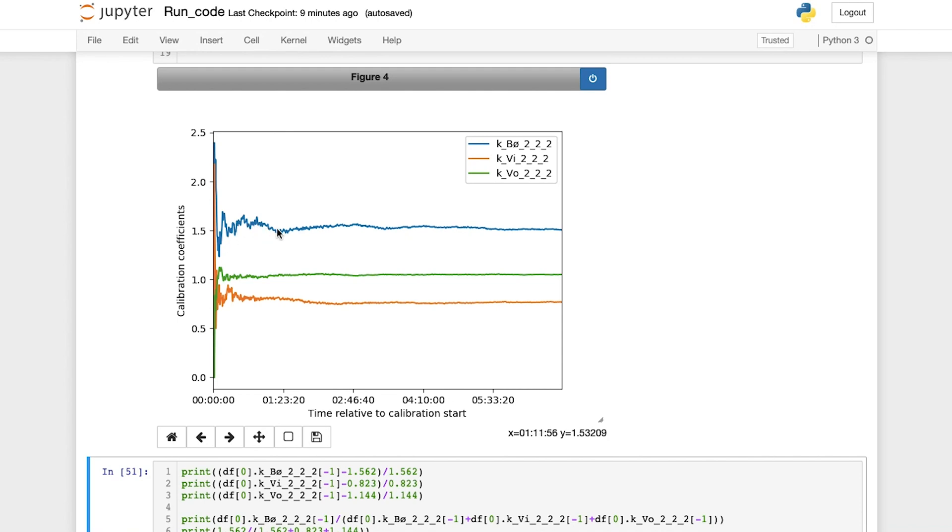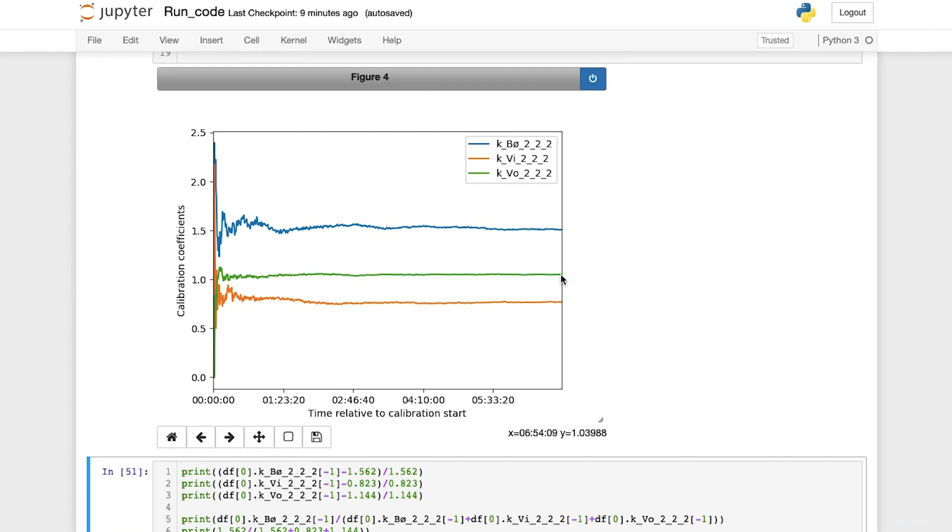In the end here, we see that these three lines stabilize. That means the coefficients for the multiphase flow meter have stabilized, and we can confidently say that these three points represent correct calibration coefficients.